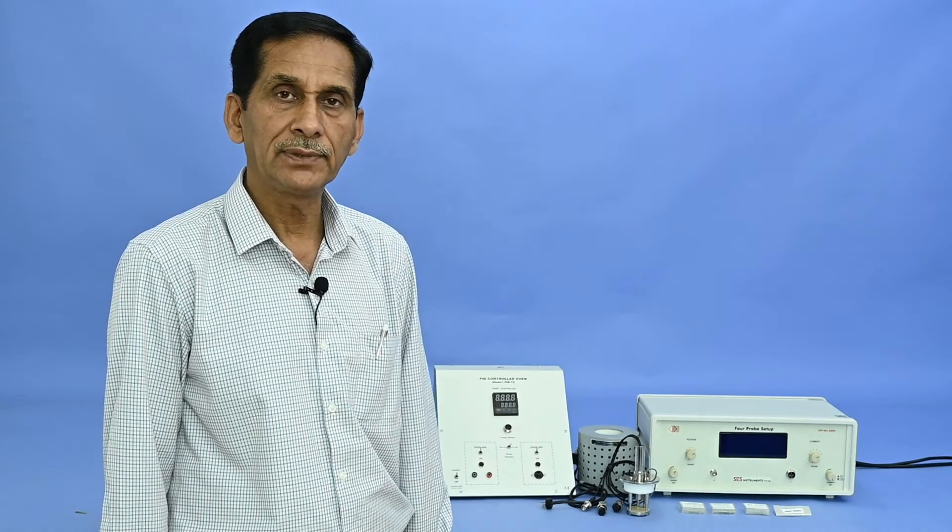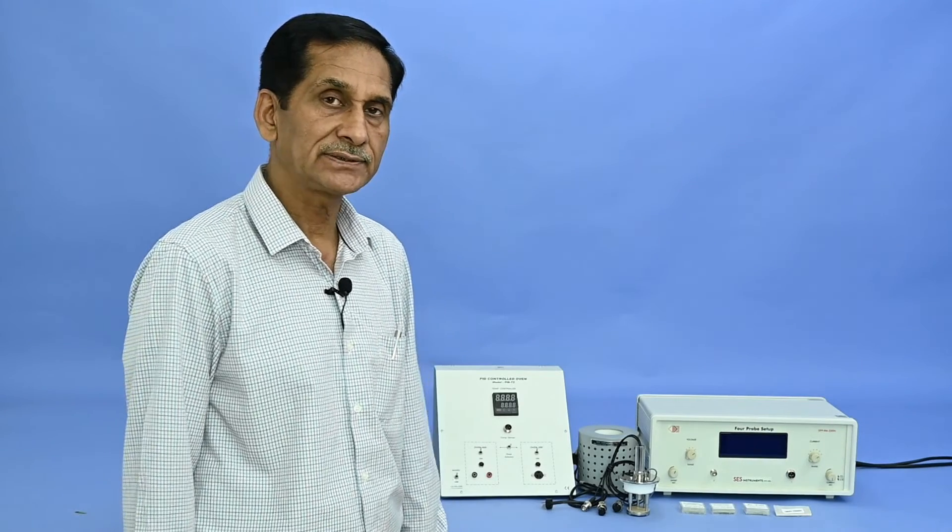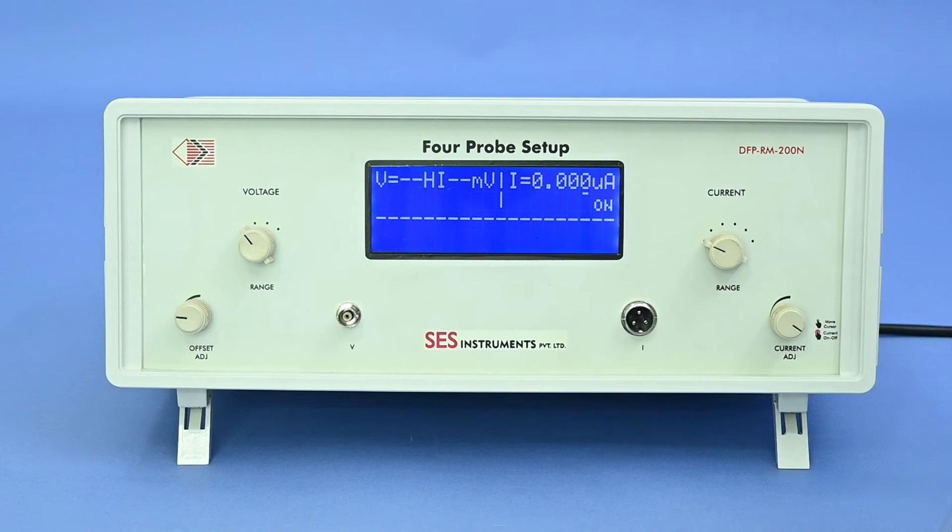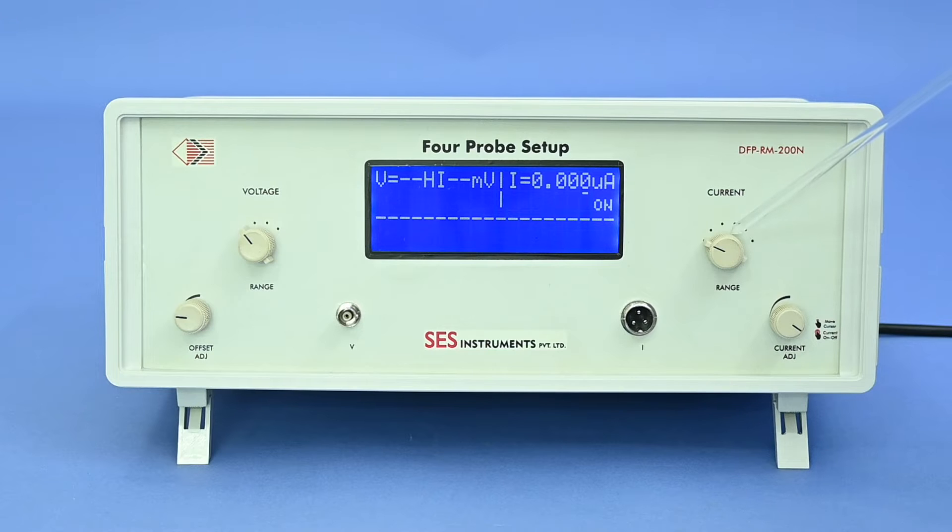When you unpack the carton box, we will get the different parts of the experiment. Four probe setup controller unit, built-in constant current source and voltmeter unit. Current source range works in six decade steps: 2 microamps, 20 microamps, 200 microamps, 2 milliamps, 20 milliamps, and 200 milliamps.